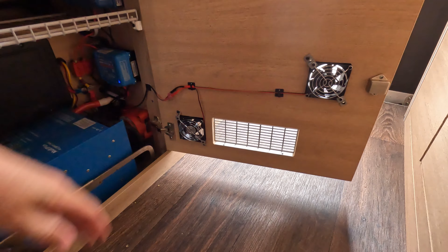The way this system works is the Victron has powered relays that you can program. So I'm going to walk you through how I program the relay to turn the fans on when the inverter fan comes on and turn them off when the inverter fan goes off.